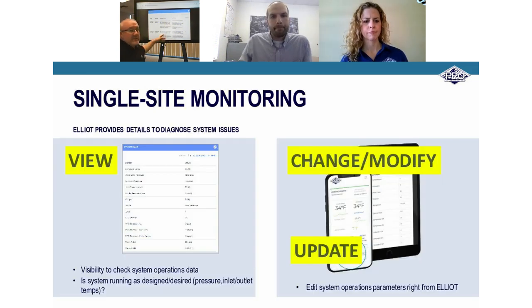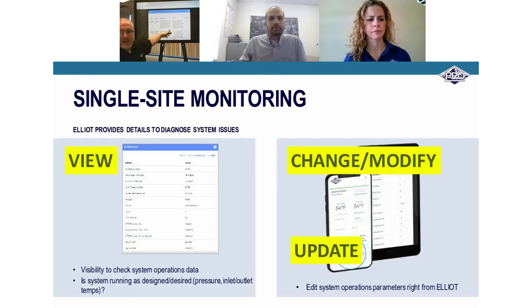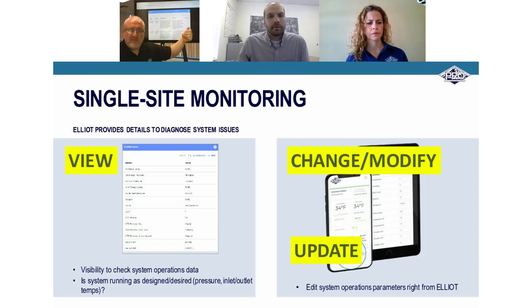Yeah, you can see on this one in particular, I've got 2 external alarms, and by checking the status of the oil pressure switch, that's because they've got a circuit breaker off to the compressor. The system called that compressor to operate, which activated the oil switch, but the oil switch tripped because the compressor is not running and building oil pressure. So it doesn't dig in that deep, but it does say, hey, go look at your oil switch.